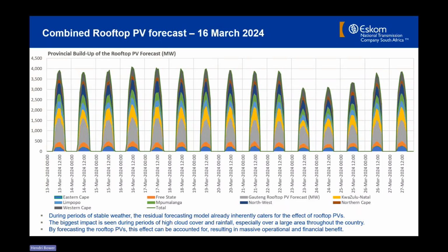Please. We actually started looking at the ramp rates of the demand, and exactly for that reason, because it's obviously something that we are starting to get more and more concerned about, especially because if you look at the timing of your PV generation, it's smack bang in the middle of the day, which means that it reduces the amount of energy that we need to supply during that period significantly. But then towards the evening peak, when the rooftop falls away and obviously starts to get dark, then there's quite a steep pickup into our evening peak.